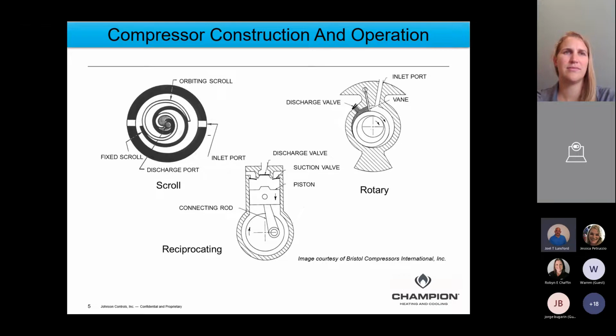So yeah, there's different compressor technologies, but from a manufacturing and from a practical standpoint, up to probably 50 or 60 tons of air conditioning capability, you'll never see anything except scroll compressors or those types of technologies. You don't start getting into centrifugals till you get into like 150 ton, 200 ton air conditioning, and you don't start getting into the screw compressors until you get into some of the big, huge, low temperature ammonia systems. Typically those will have a screw type of compressor.